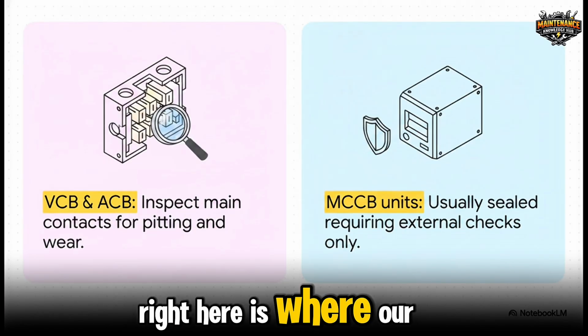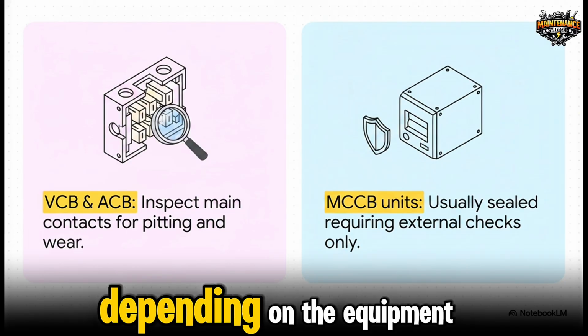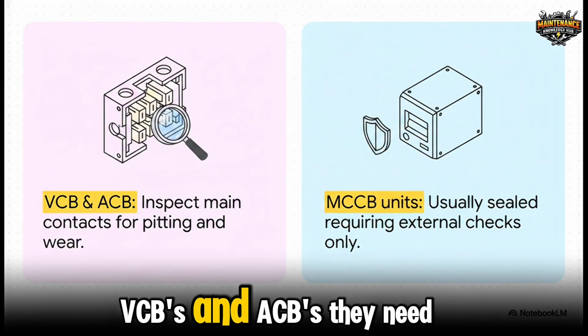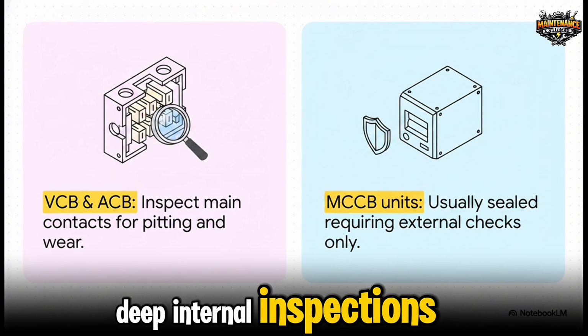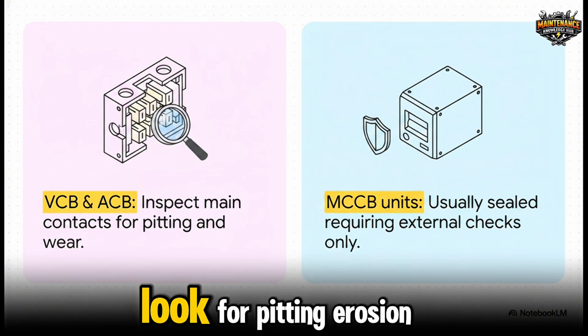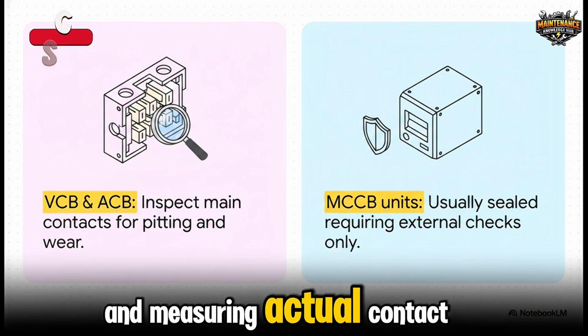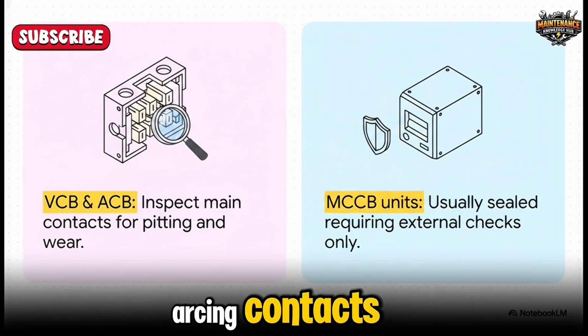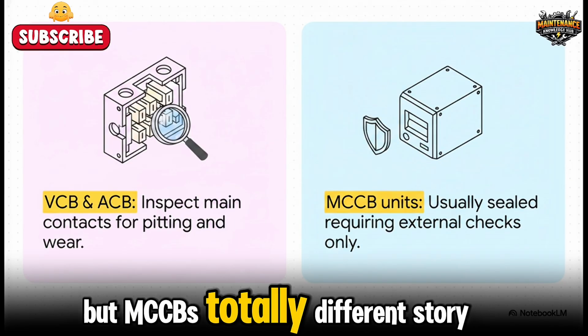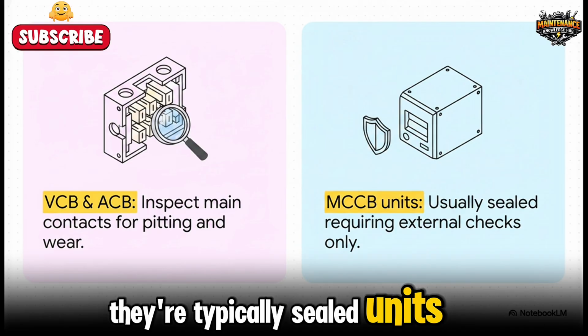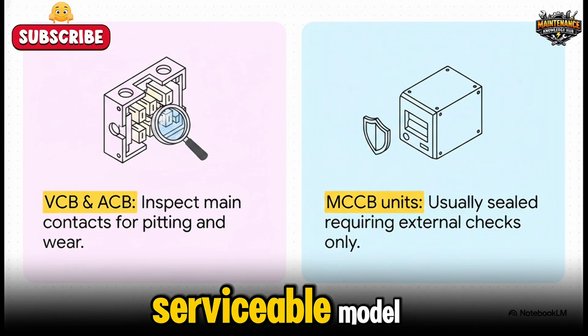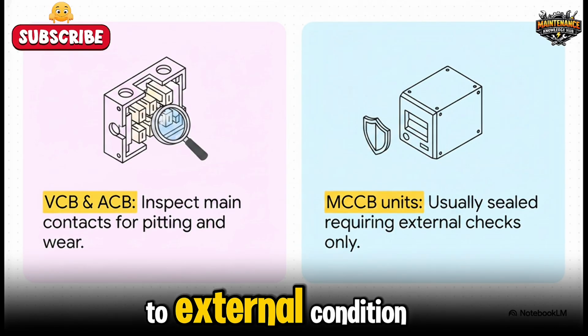Now, right here is where our routine really splits, depending on the equipment. VCBs and ACBs, they need deep internal inspections. You're getting in there to specifically look for pitting, erosion, and measuring actual contact wear on the main and arcing contacts. But MCCBs, totally different story. They're typically sealed units. Unless you've got a specifically serviceable model, you're pretty much just sticking to external condition checks for those.